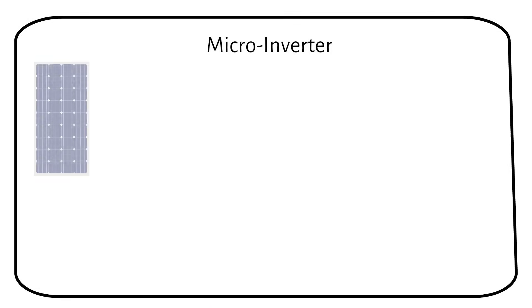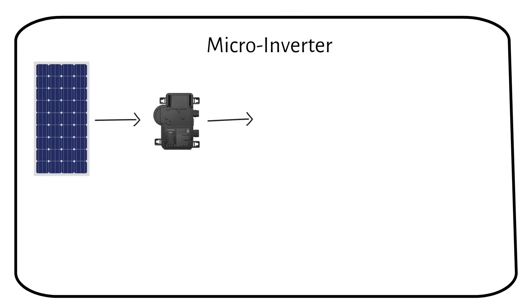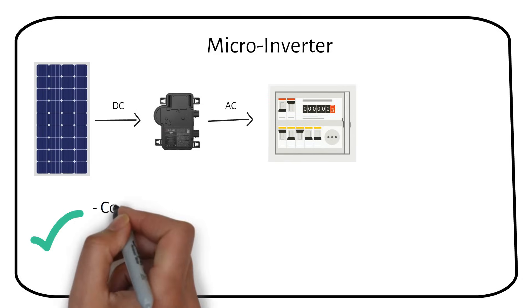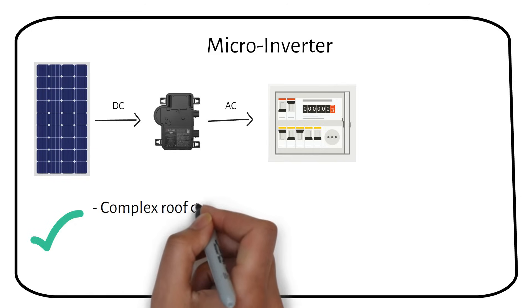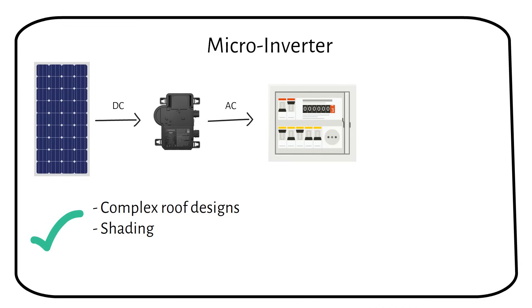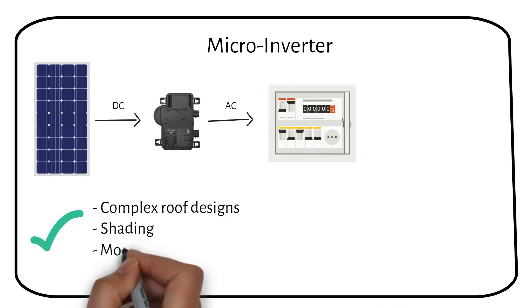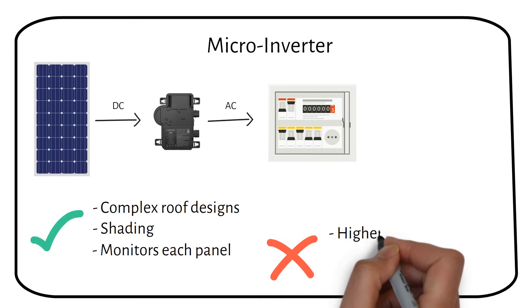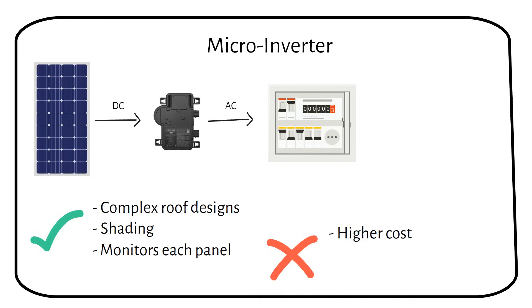A micro inverter is a small device installed behind each solar panel that converts the direct current produced by the solar panel into alternating current that can be used in your home. These devices are used in residential settings, especially in homes with complex roof designs or areas affected by shading. With micro inverters, only the performance of the shaded panel decreases without impacting the entire system output. Additionally, they offer the advantage of monitoring each panel individually, providing detailed insights into the performance of your solar installation. Micro inverters do come with a higher price tag compared to traditional string inverters.